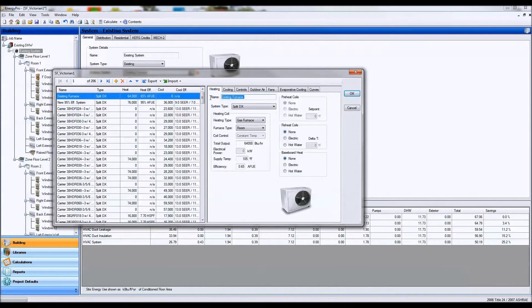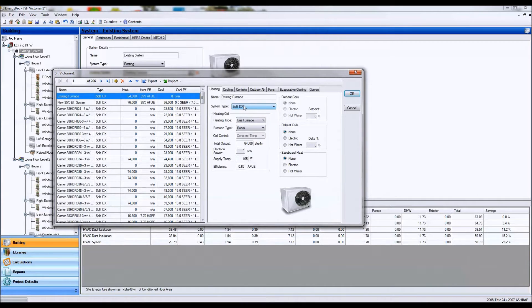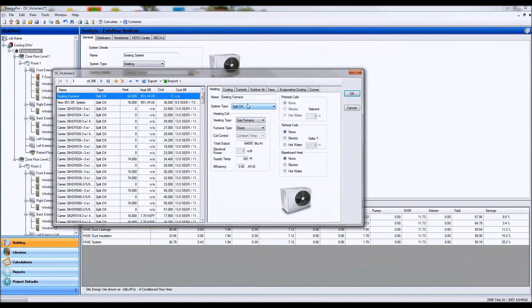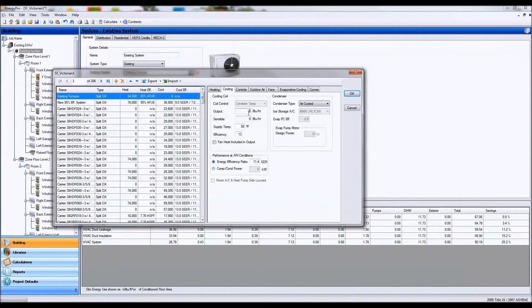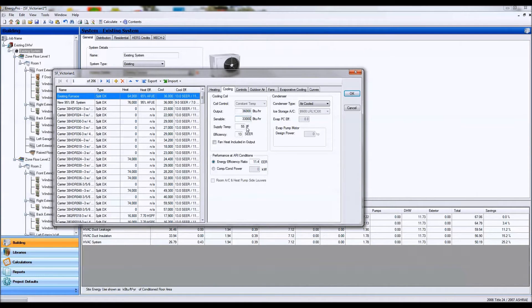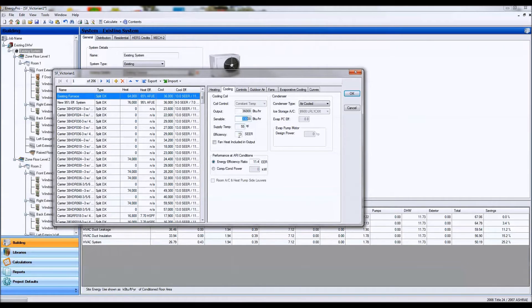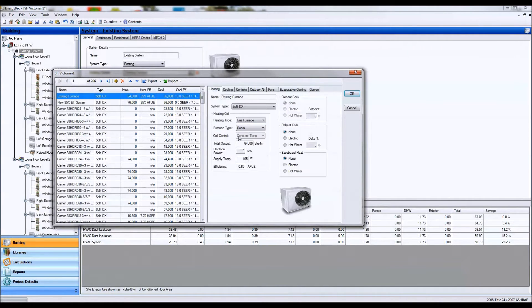So again, name it accordingly. And let's first look at the typical type of systems found in most homes, which is a split system, which has a furnace in the garage or attic crawl space and an air conditioner outside. So let's go ahead and model our air conditioner in as a three ton unit. The sensible is a little bit lower than the output, but you don't really need to put that in as any particular number for calculation. The efficiency should be based on the name plate or the vintage based on the building.